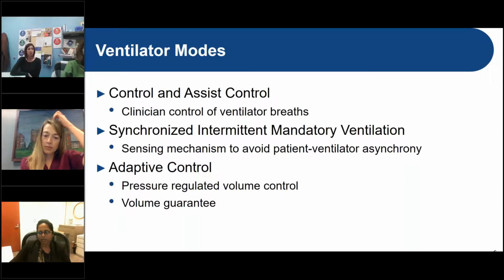SIMV, or synchronized intermittent mandatory ventilation, is a mode of ventilation that allows the clinicians to again set a rate, a size of the breath, and a time that the breath is administered, but it also synchronizes these breaths with the patient's spontaneous breathing. And then we have the adaptive controlled breaths, which are pressure regulated volume control. Again, the clinician will set a rate, and they will set a size of the breath in volume, and they will also set the amount of time it takes to deliver that breath. What it will do is, over a certain amount of breaths, usually about 3 breaths, it will try to control the amount of pressure it takes to deliver those breaths, delivering the smallest amount of pressure possible to minimize trauma to the lungs.